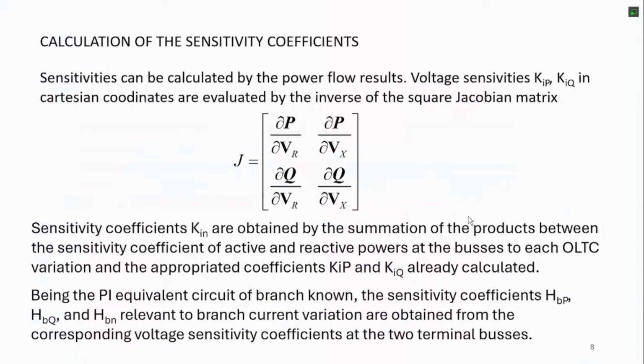We are not including the voltage at the slack bus, the connection to the transmission network, since we consider it fixed on the primary side of the substation. So the matrix is squared and you can take the inverse, giving the relationship between voltage and active and reactive power. We can do the same for the taps in the transformers, since the sensitivity coefficients of active and reactive power at the buses to each OLTC variation can be calculated, giving the relationship between the tap and the power.